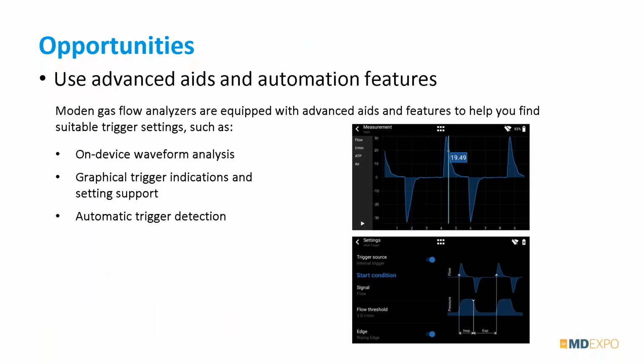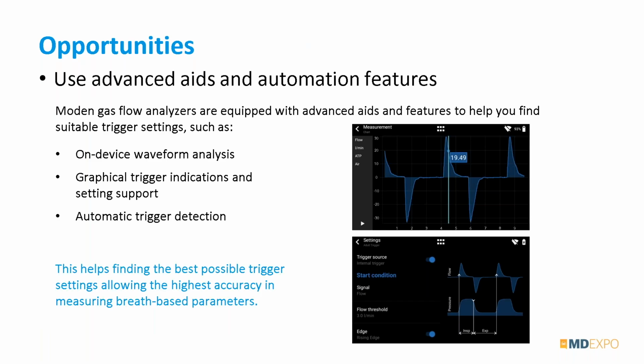And in the latest generation of gas flow analyzers, there's also something called auto triggering. So they can analyze the waveforms in real time and then decide themselves which one is the best one to trigger on. Just imagine how helpful that is if you have to change the trigger settings based on the settings on your ventilator you have to test. Okay, so very important, make sure that you check what your gas flow analyzers have to offer as helps to figure out all these settings.